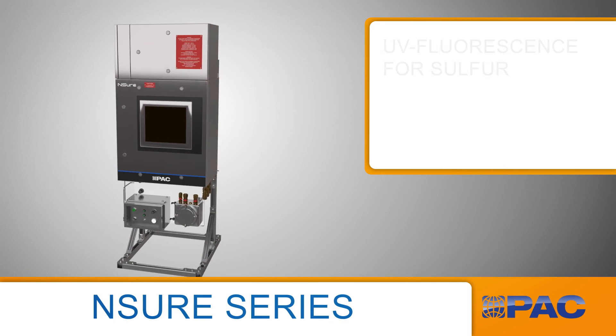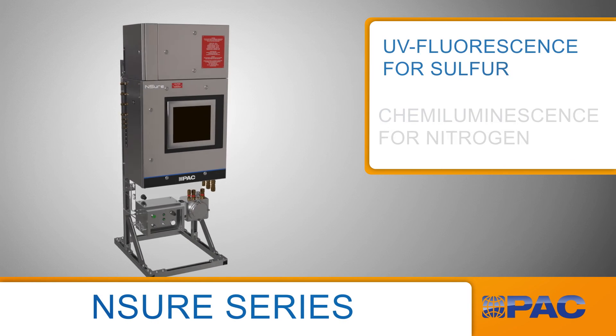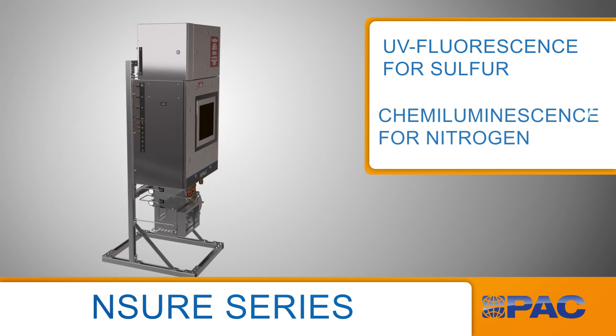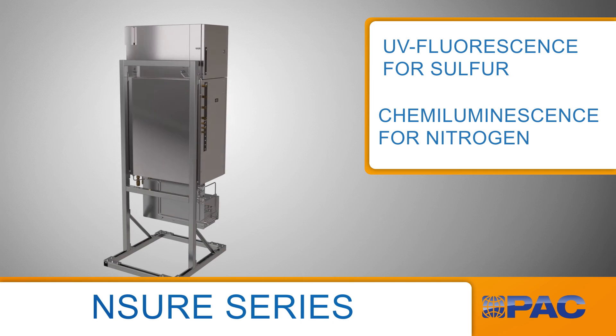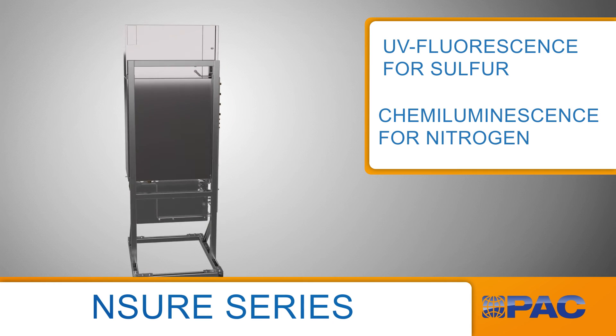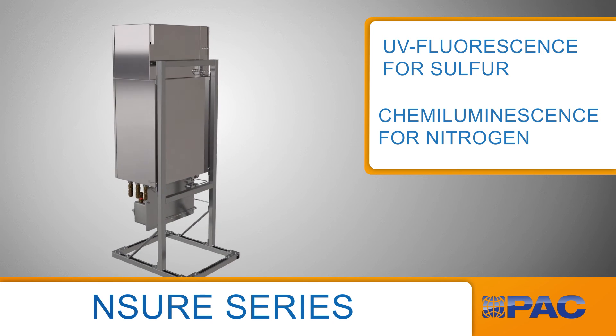Nsure uses UV fluorescence for sulfur detection and chemiluminescence for nitrogen detection. The process involves combusting a sample, exciting the molecules, and measuring the light emitted.